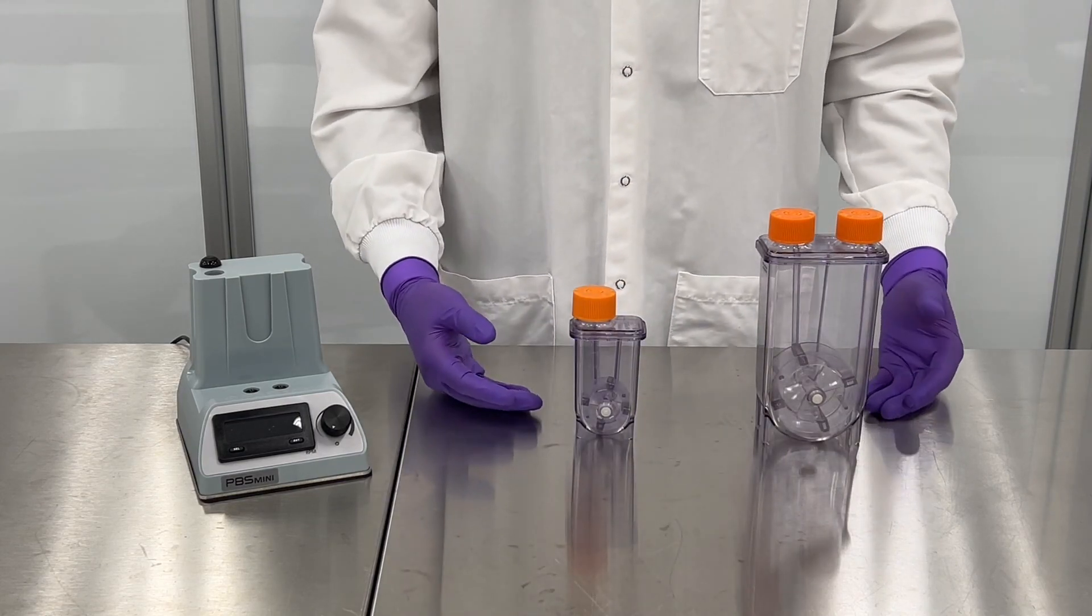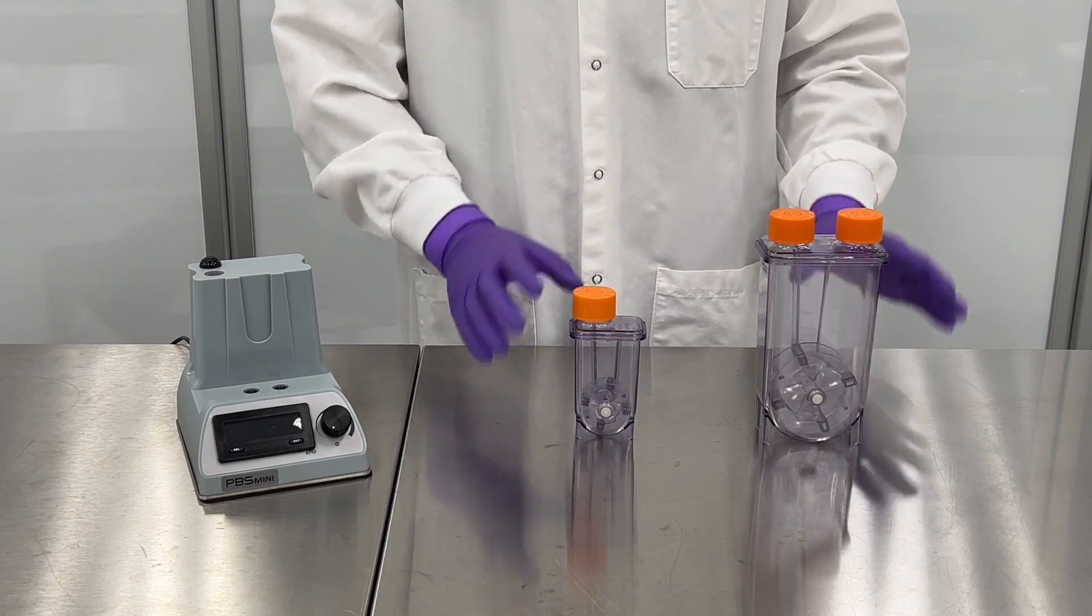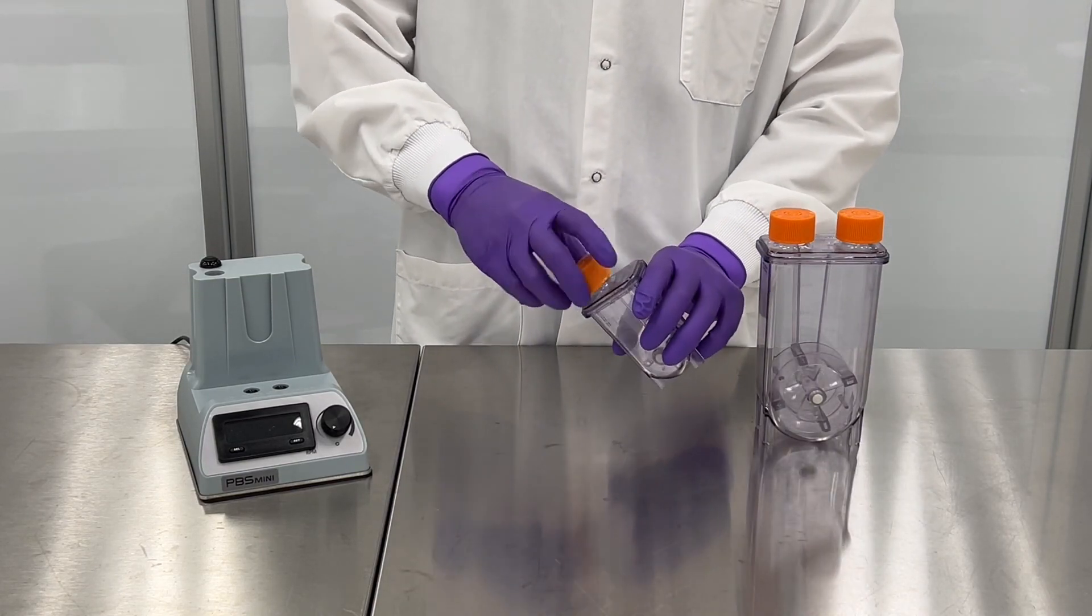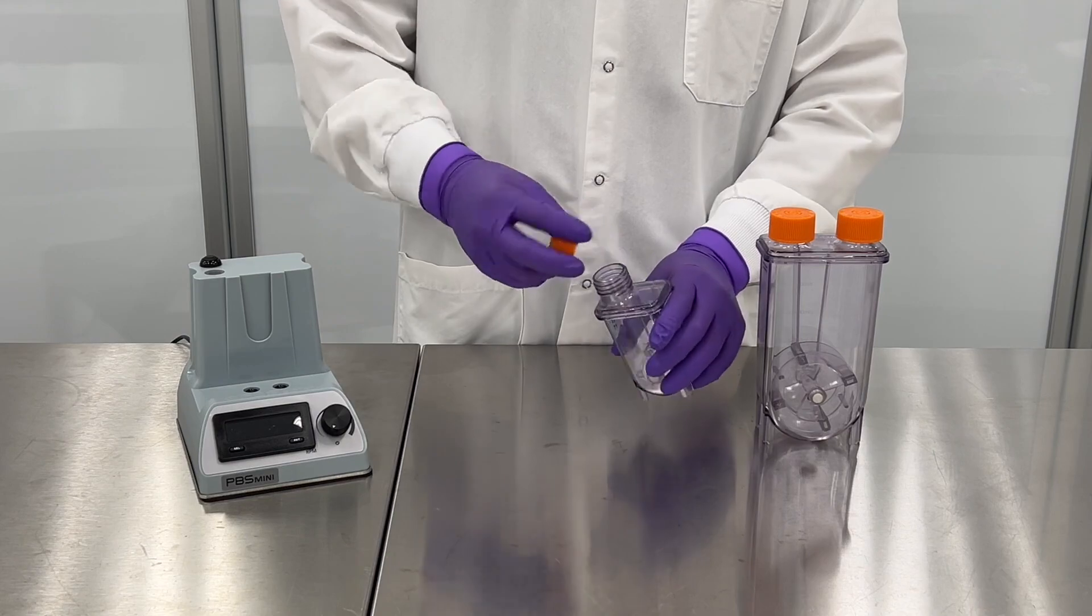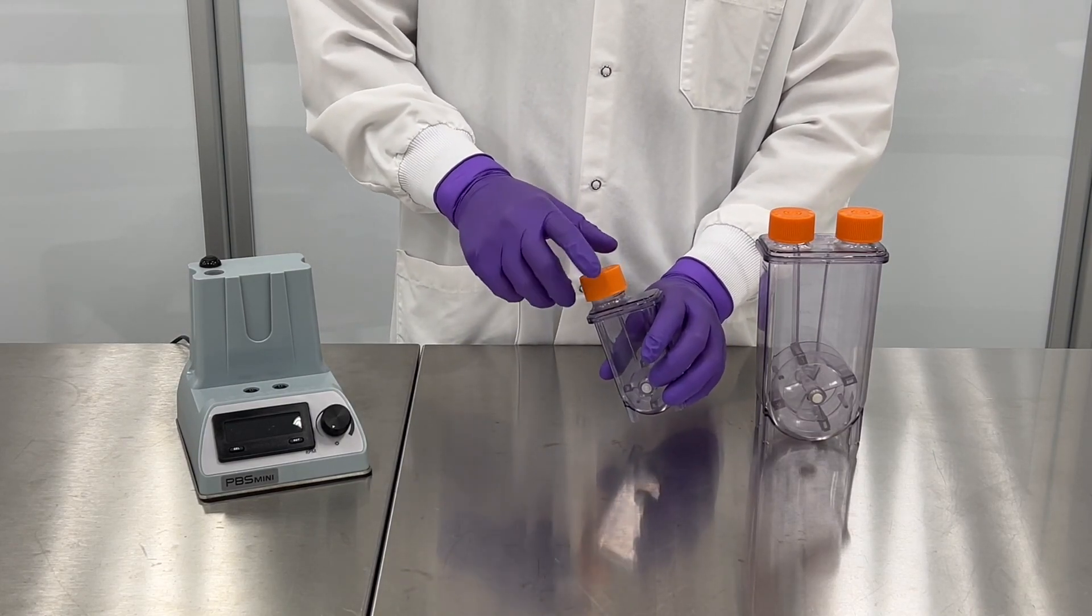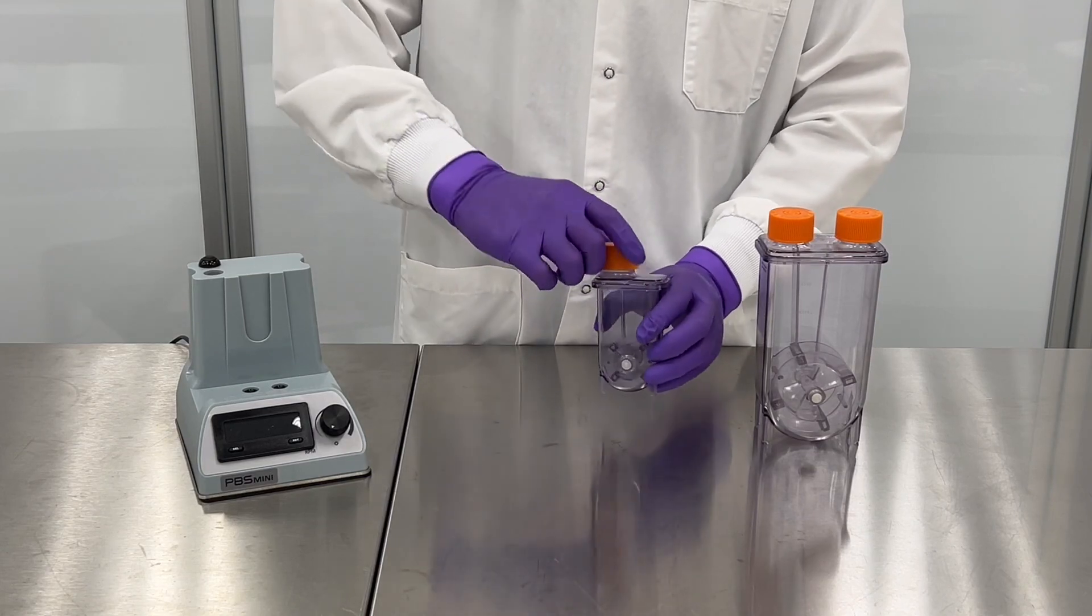The exterior of the body, these are both single injection molded polycarbonate pieces with tops and then up top here we have our vented cap. So this is a 0.2 micron vent and to put this on all you do is twist it on gently and you don't have to wrench this on. There's no compressible bits so it's just finger tight.